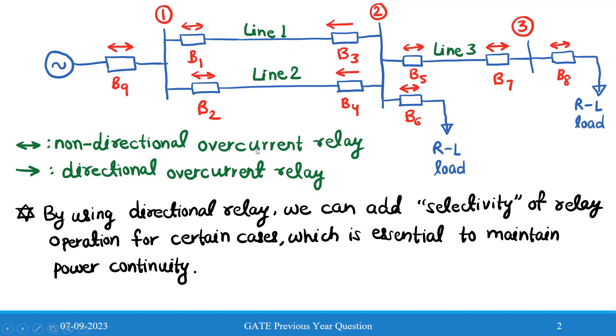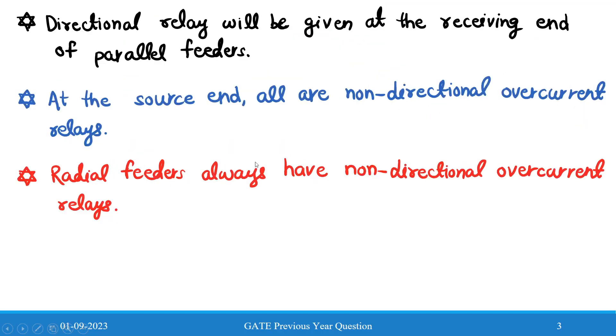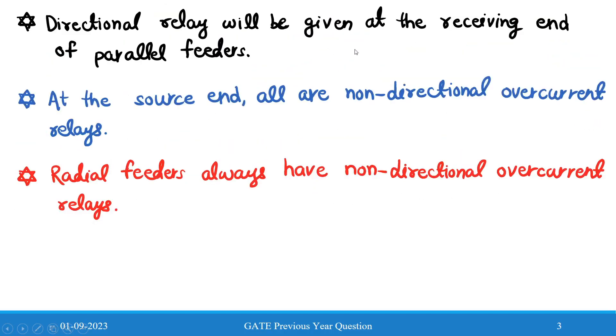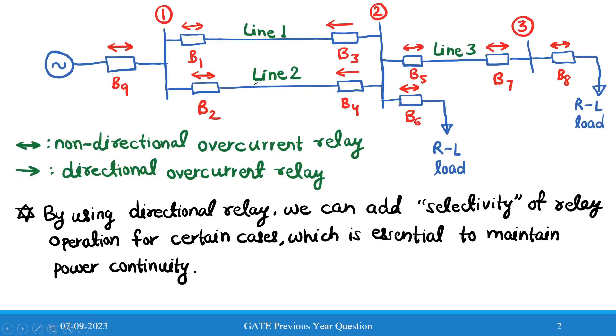I have noted three important points for choosing directional versus non-directional relays in the circuit. The first point is that a directional relay will be placed at the receiving end of parallel feeders. We have parallel feeders line one and line two, so the directional relays will be at the receiving end — therefore B3 and B4 will be the directional relays.